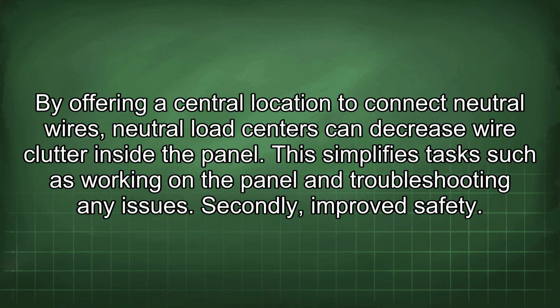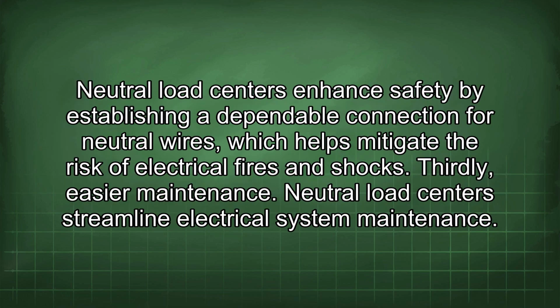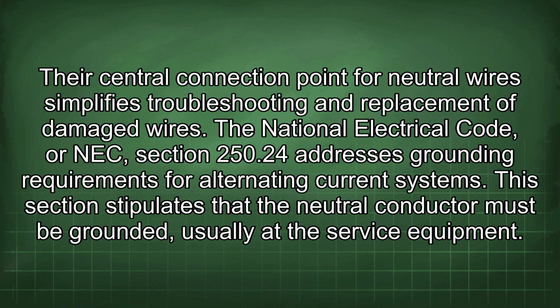Secondly, improved safety. Neutral load centers enhance safety by establishing a dependable connection for neutral wires, which helps mitigate the risk of electrical fires and shocks. Thirdly, easier maintenance. Neutral load centers streamline electrical system maintenance. The central connection point for neutral wires simplifies troubleshooting and replacement of damaged wires.